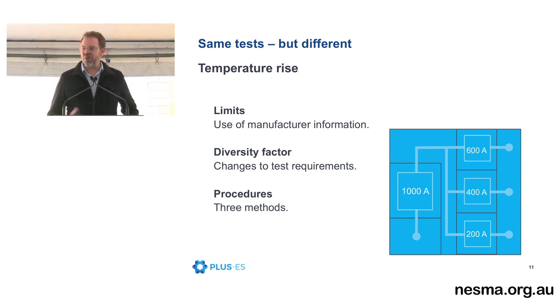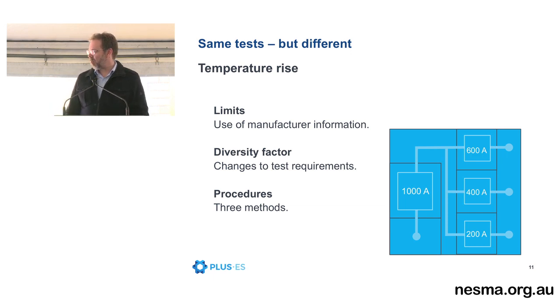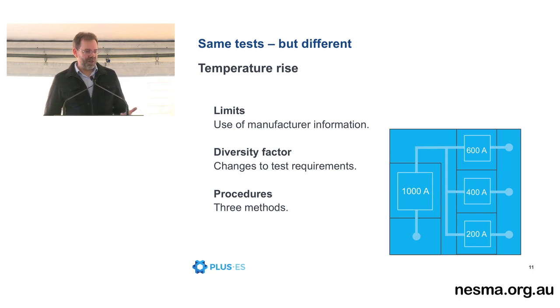The new standard sort of takes care of that anomaly by requiring, if you assign a diversity factor to an outgoing unit, you now need to prove that the outgoing unit running on its own, because remember, diversity factor is for a group of outgoing units really.